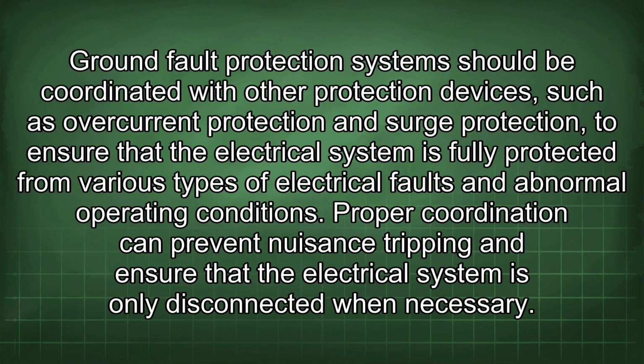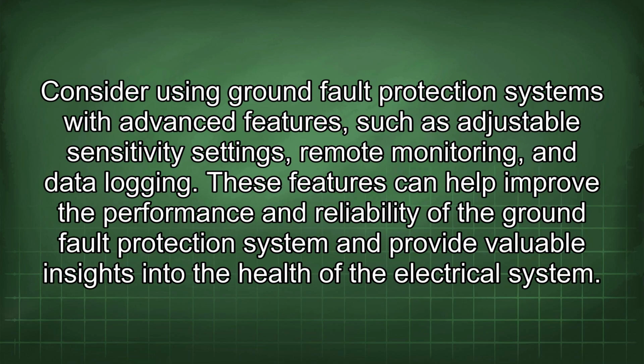Ground fault protection systems should be coordinated with other protection devices, such as overcurrent protection and surge protection, to ensure that the electrical system is fully protected from various types of electrical faults and abnormal operating conditions. Proper coordination can prevent nuisance tripping and ensure that the electrical system is only disconnected when necessary. Consider using ground fault protection systems with advanced features such as adjustable sensitivity settings, remote monitoring, and data logging. These features can help improve the performance and reliability of the ground fault protection system and provide valuable insights into the health of the electrical system.